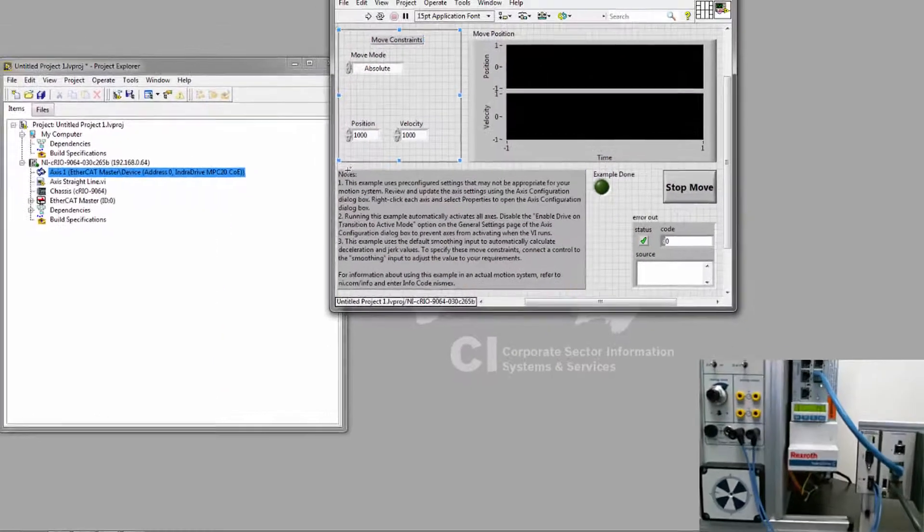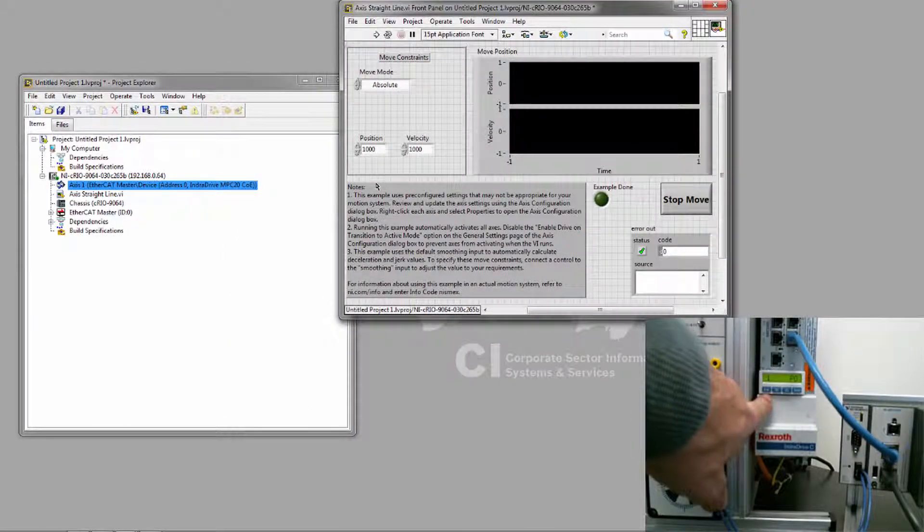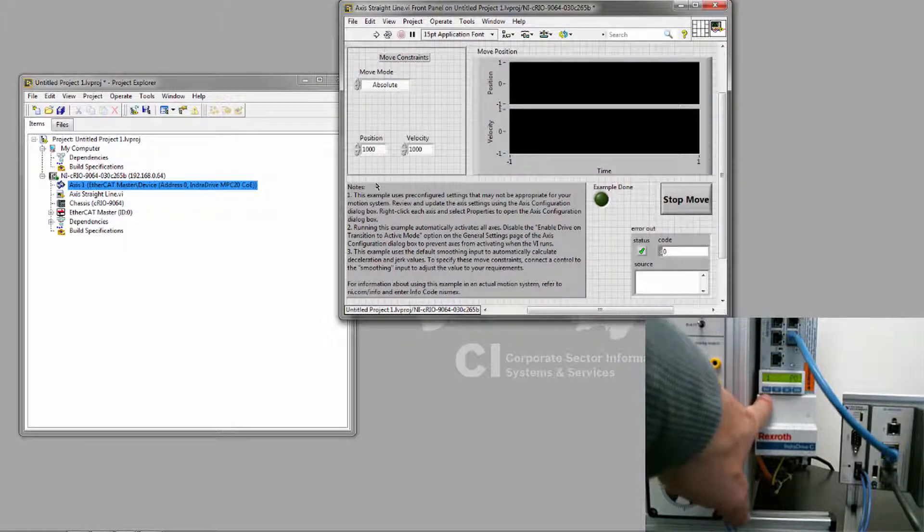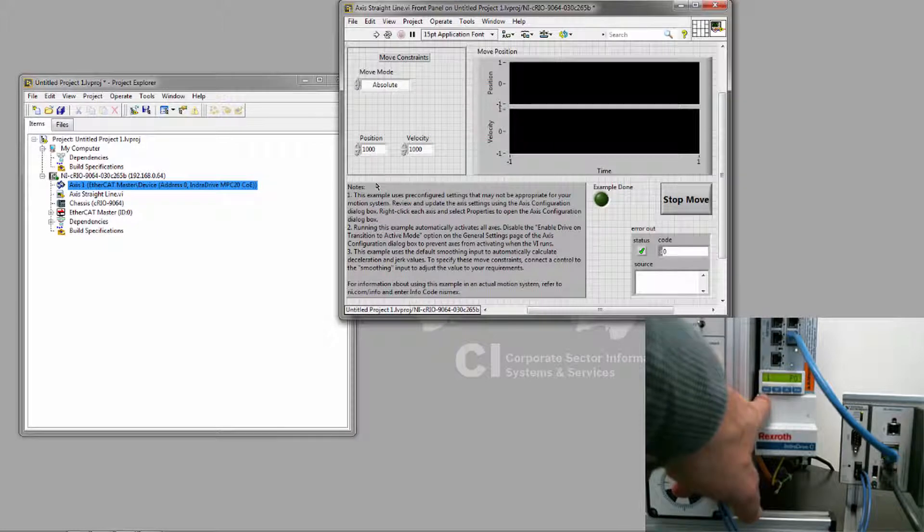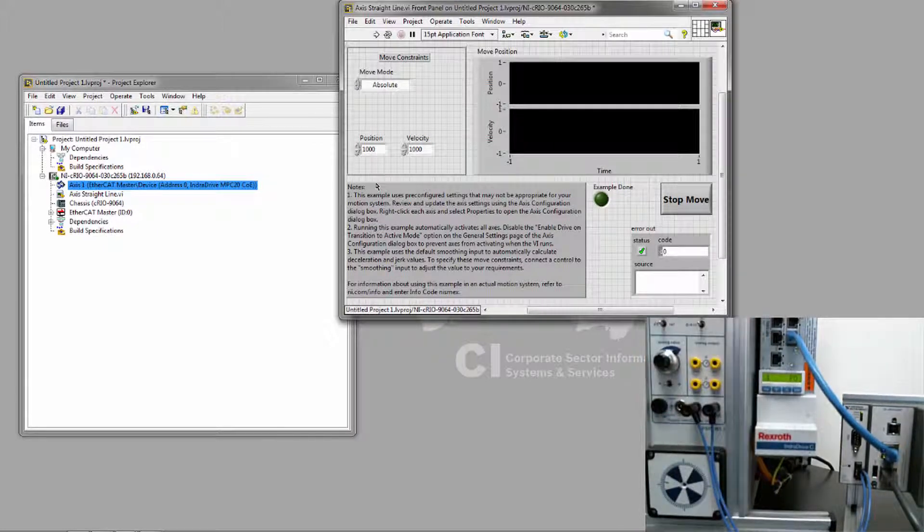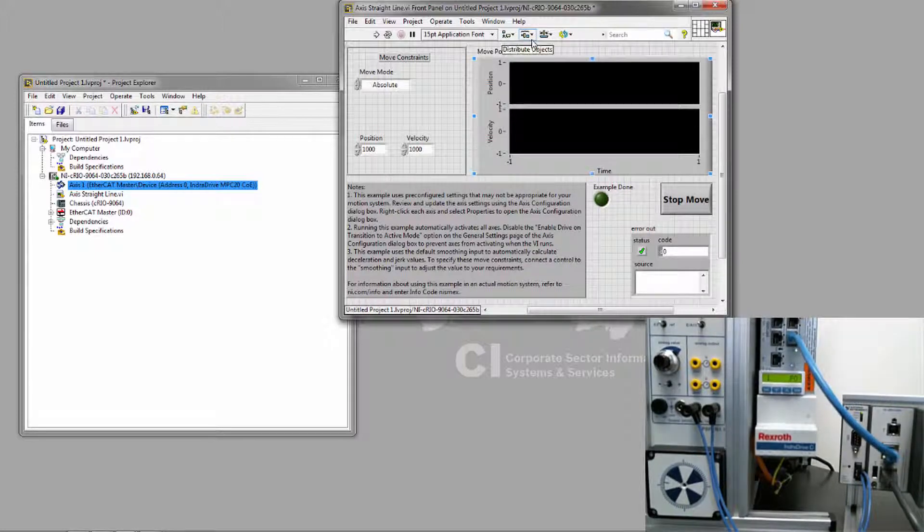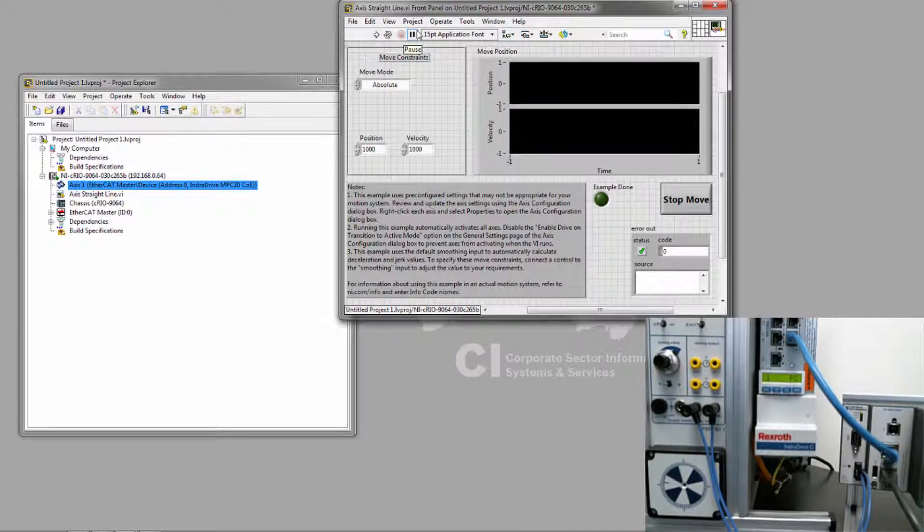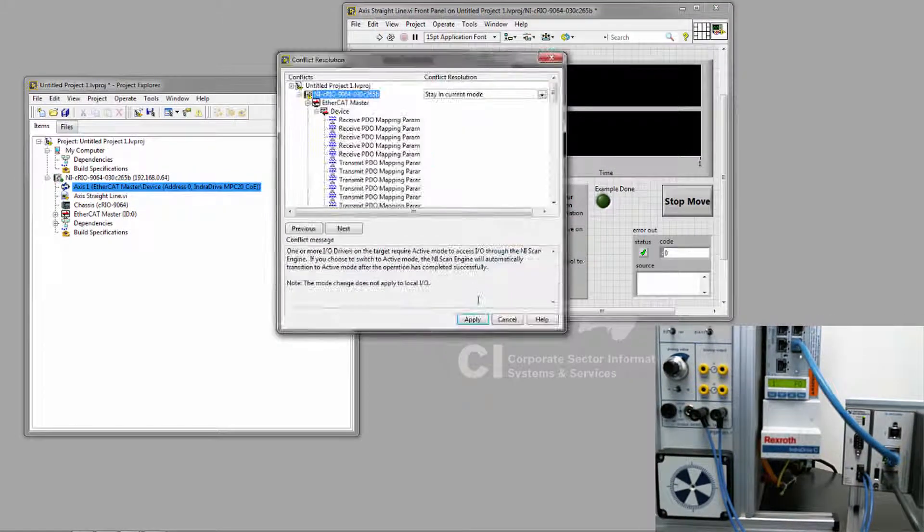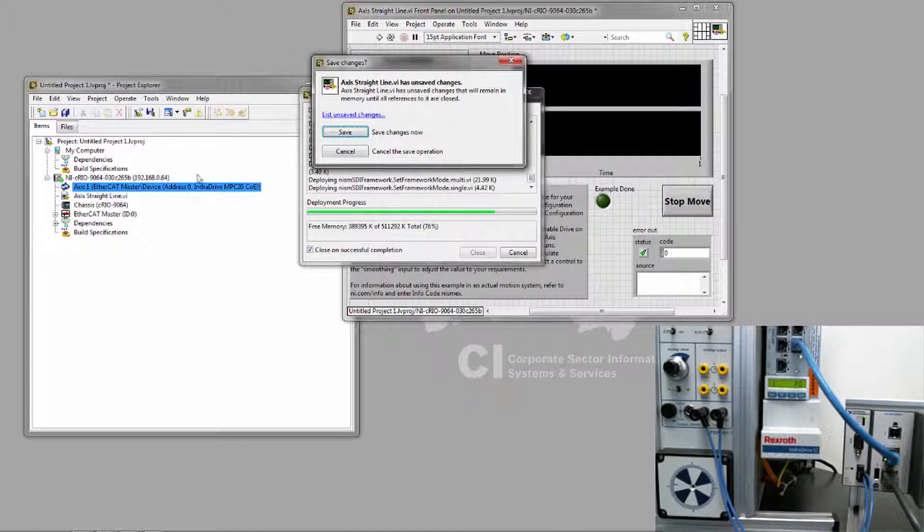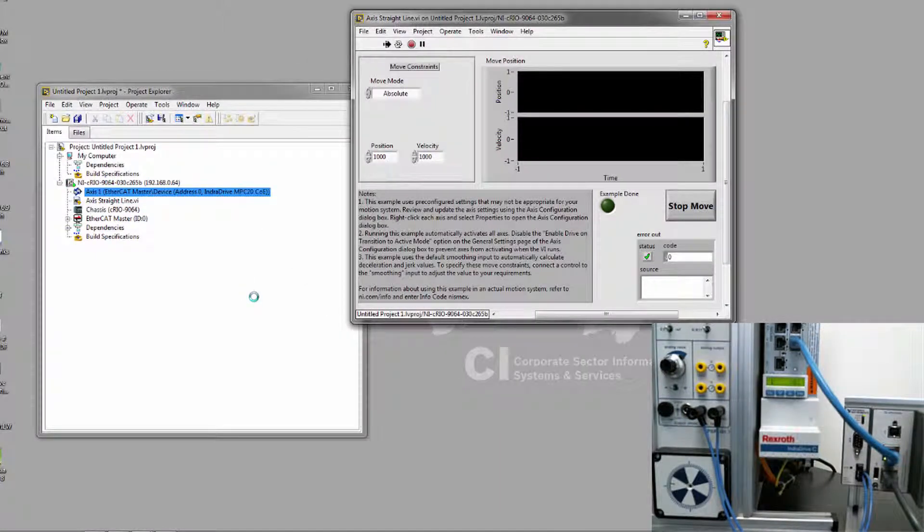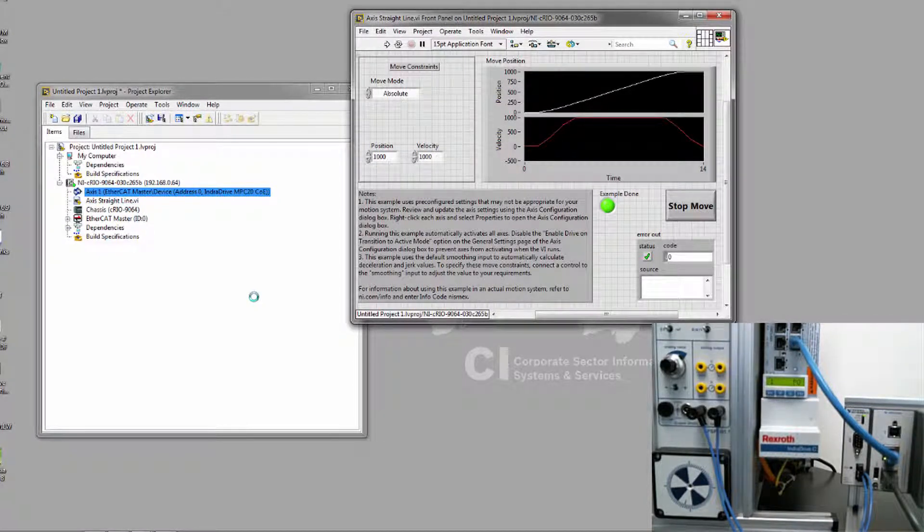And when we do, we should see the drive, the scan engine change from configuration mode. In this case, the drive will show P0 in configuration mode to active mode, in which case the drive will show AB, which means that the drive is ready for motion. And then after that, we should see the drive energize and then the motor move. So let's try to run this. So the scan engine mode is changing. We switch to AB. The motor moves, and then we switch back to configuration mode.